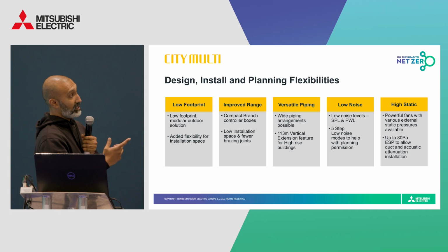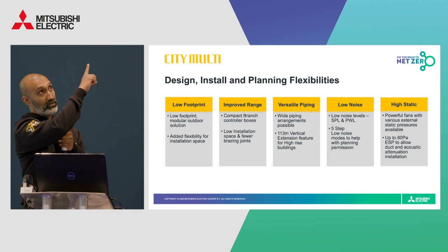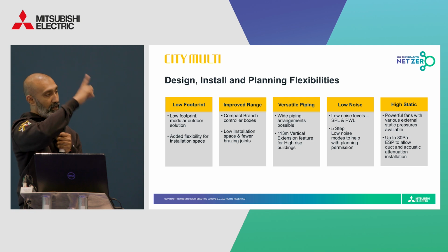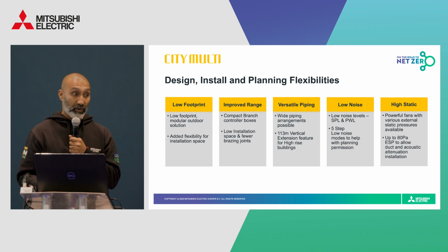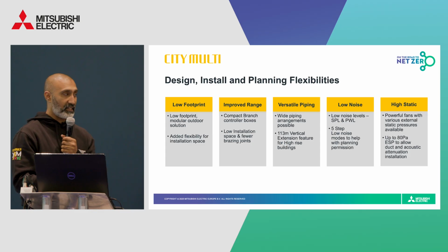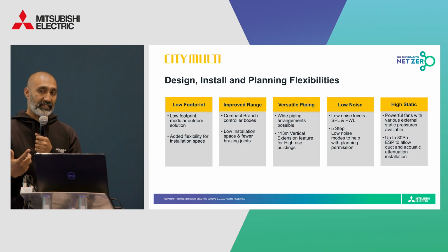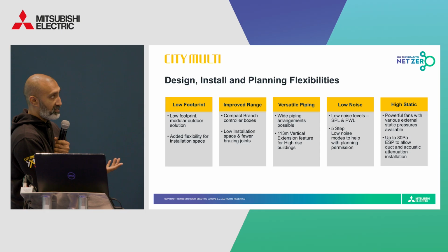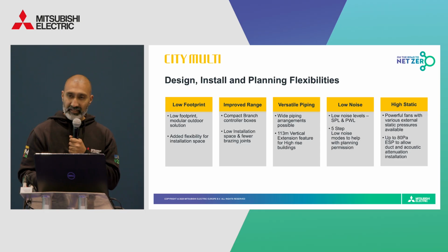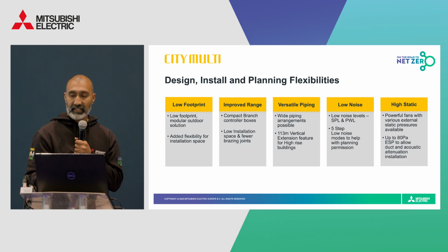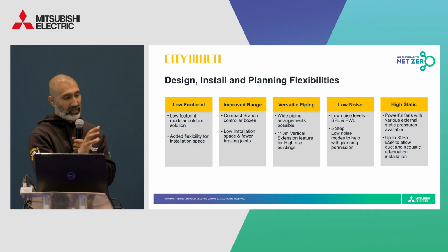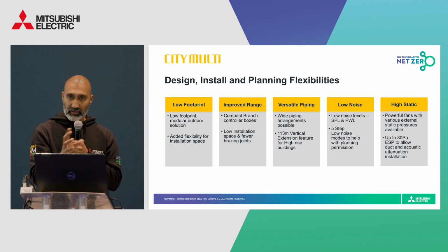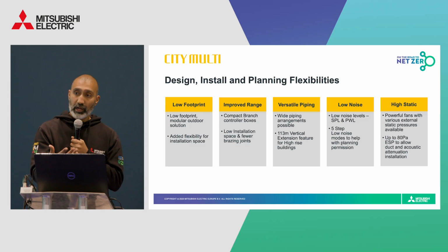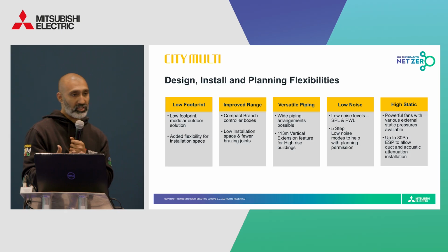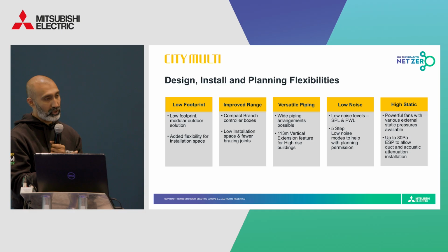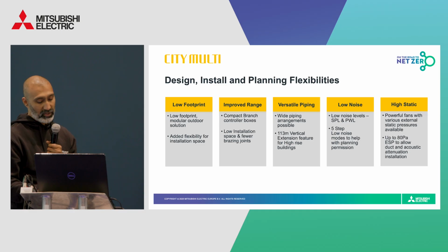And then pipe runs. So previously, the pipe run, when you had the outdoor unit above the indoor unit, the vertical pipe run was 90 meters. But seeing that we have so many more high-rise buildings, this has now been extended too. This now goes up to 113 meters. And acoustic performance. This is another key consideration in projects, and our 5-step low noise mode allows you to really easily customize the sound levels. And then for even more control, we offer an 80 Pascal static pressure option, which again is perfect for plant room installations or when any acoustic enclosures are needed.